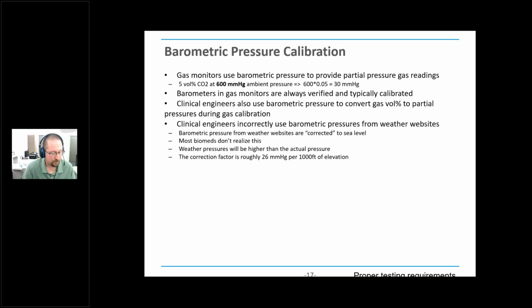But what we found in the researching and talking to people is a lot of clinical engineers don't realize that all the barometric pressure coming from websites is corrected to sea level. So if you're getting on and checking the weather pressure, those aren't accurate, absolute barometric pressures. And so you're actually off. You're off 26 millimeters of mercury total per 1,000 feet. And so you can end up calibrating your device incorrectly if you're using those readings.